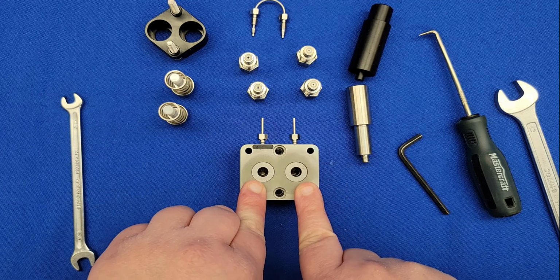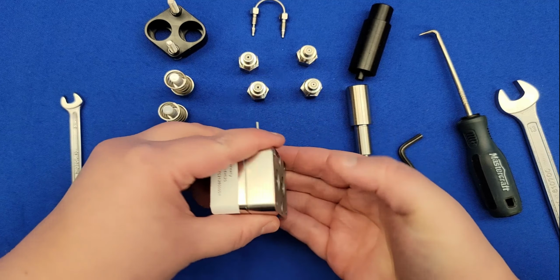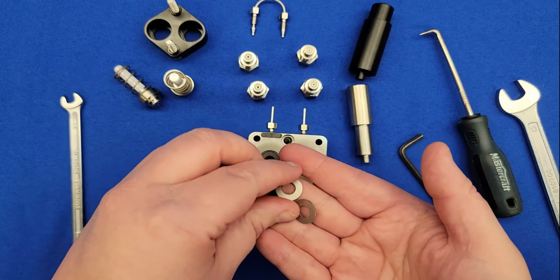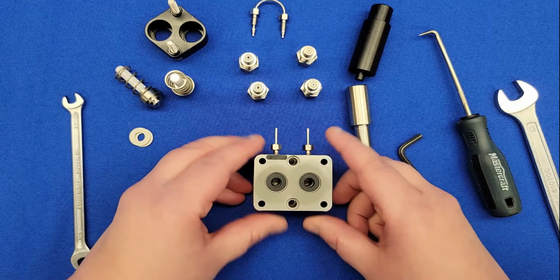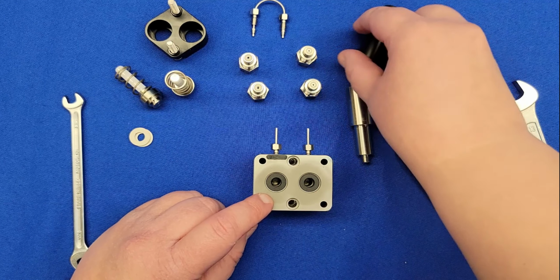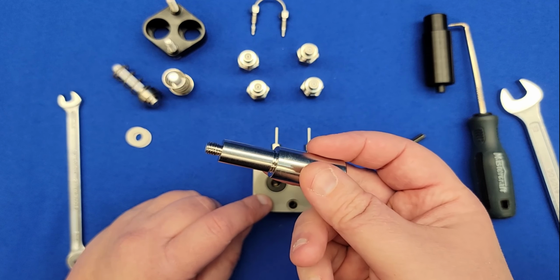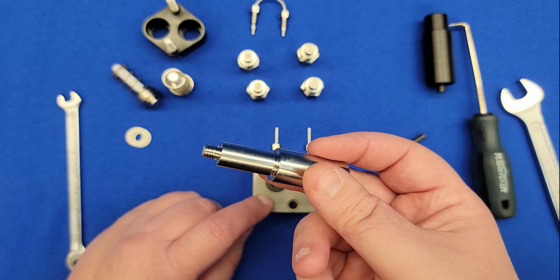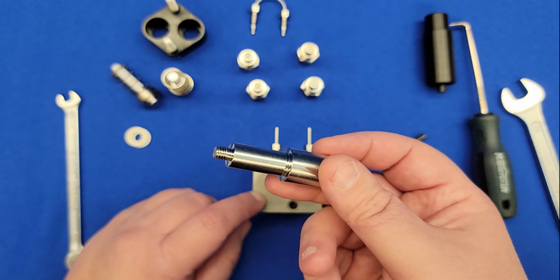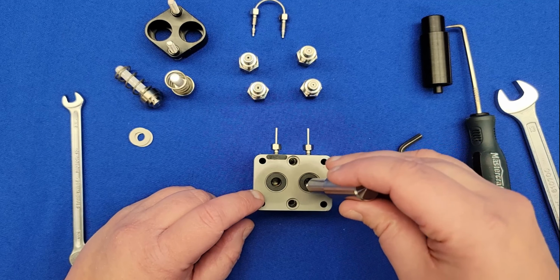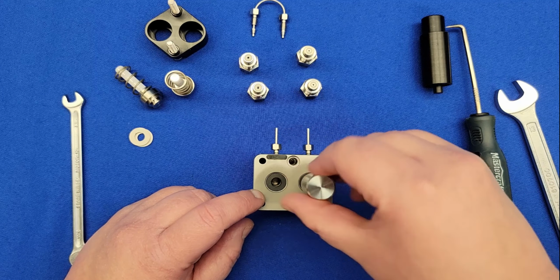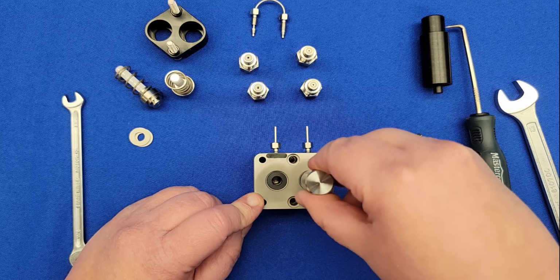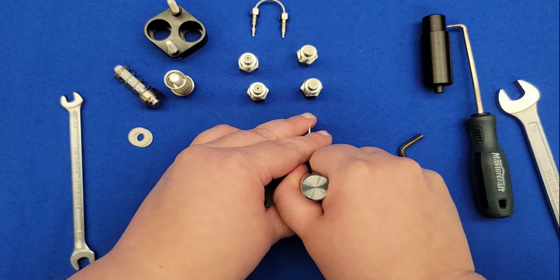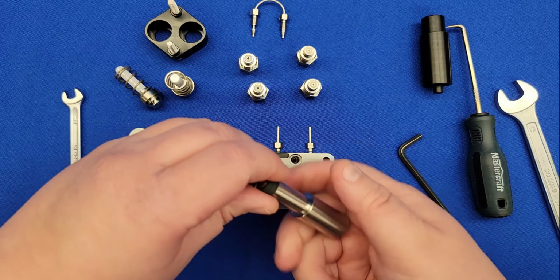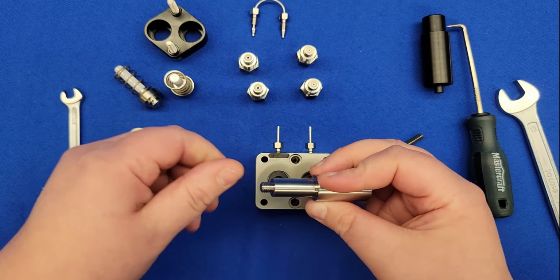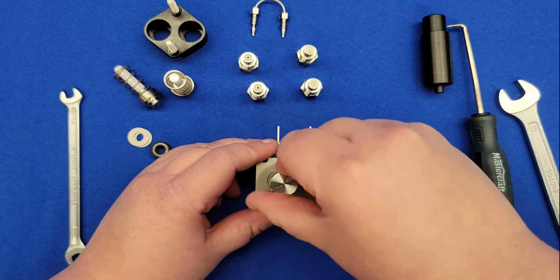Right here we have 2 metal O-rings, so we just flip this aside and they should pop right out. Then we have some seals — to remove them you use the remover tool, which comes in different sizes depending on which pump head you have. This one is for the 50 mil seals. You put it in, screw all the way to the bottom, and then pull. There you go — unscrew it, and then do the same thing over here.